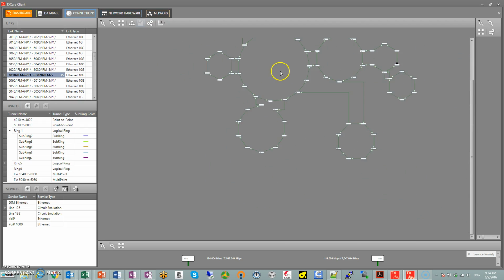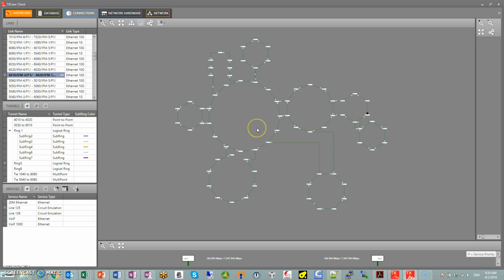In this case, one thing that maybe we don't want to do is create an RS232 point to multipoint that would reach out to all of these nodes, because it would just be too slow. If you had to poll each one of these remote RTUs, assuming there's one per site here, it would take too long. So again, we segregate the network, and we're going to try to create an RS232 port at the control center that is connected to some 20 RTUs or so.